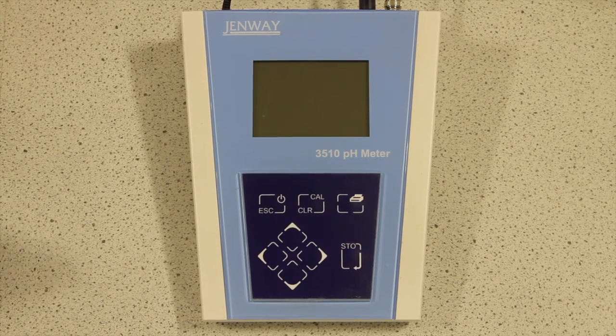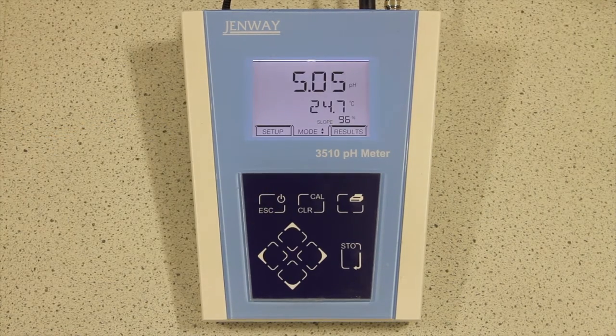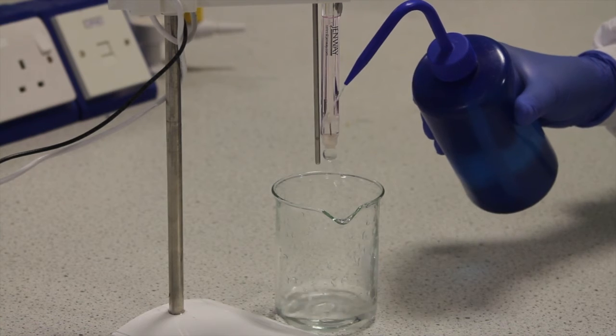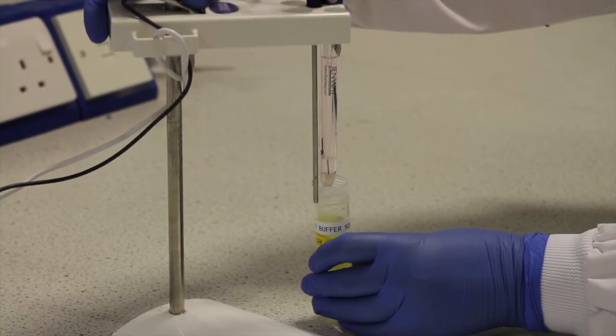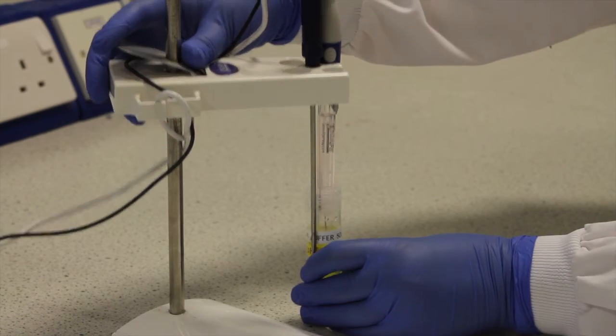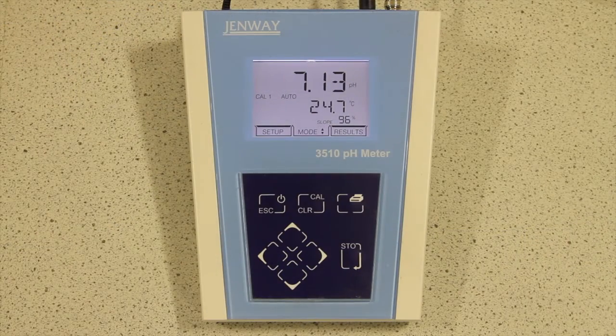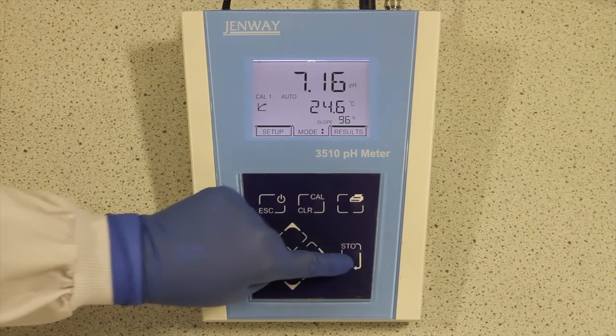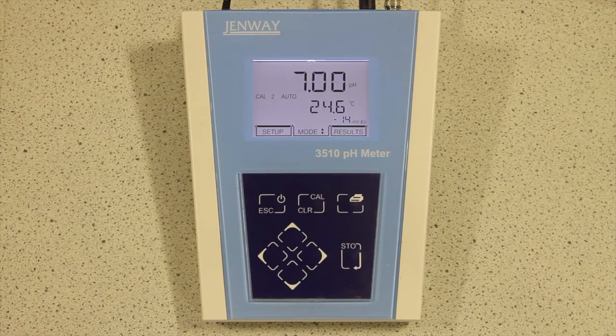To use the pH meter, start by turning it on and allow the display to settle. Press the Cal button to start the calibration. When Cal 1 is displayed, rinse the electrode in deionized water and place it in the pH 7 solution. The reading will stabilise until the endpoint symbol is displayed. Now press the STO button and the display will change to pH 7. Cal 2 will also be displayed.